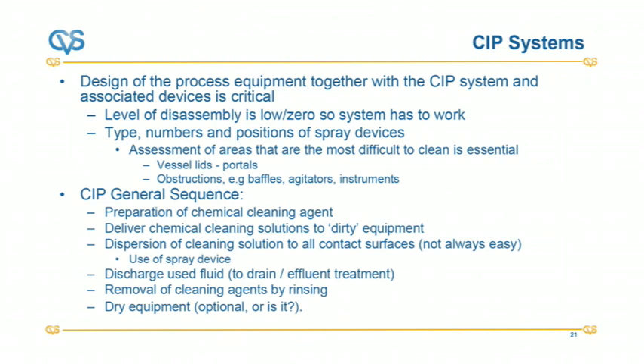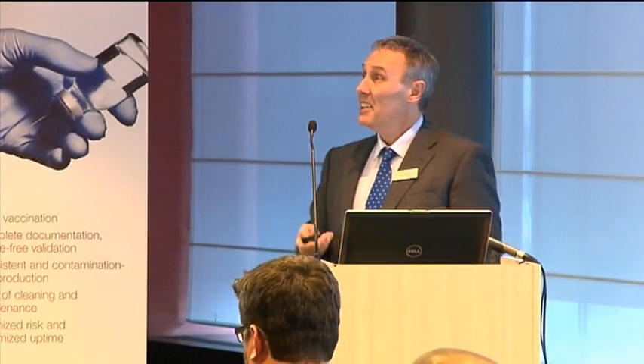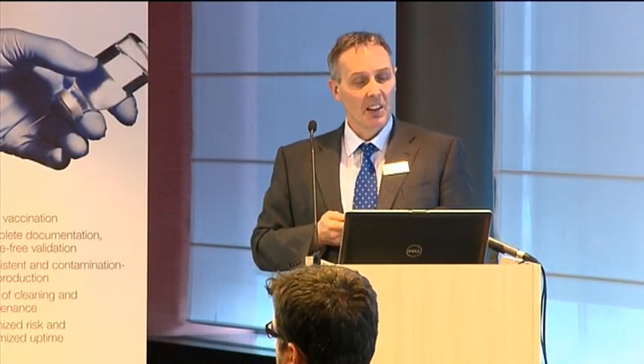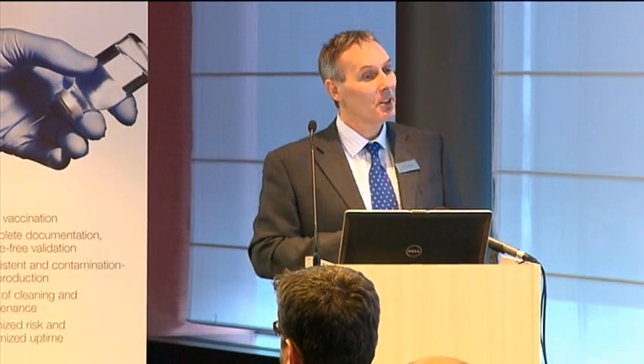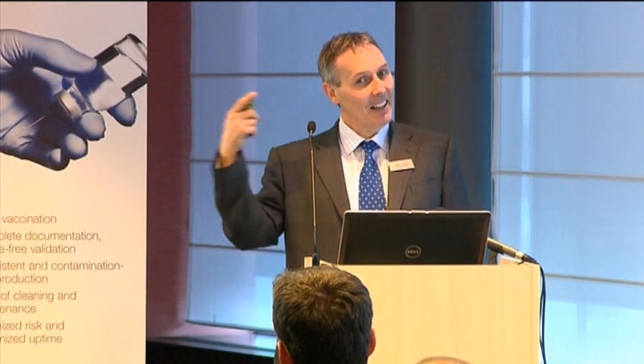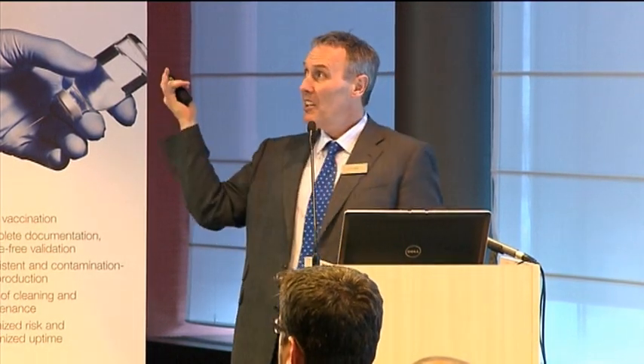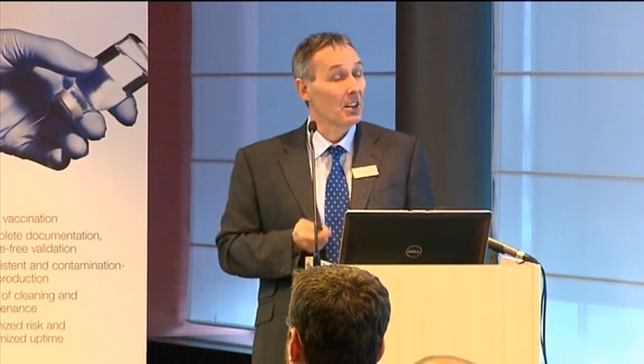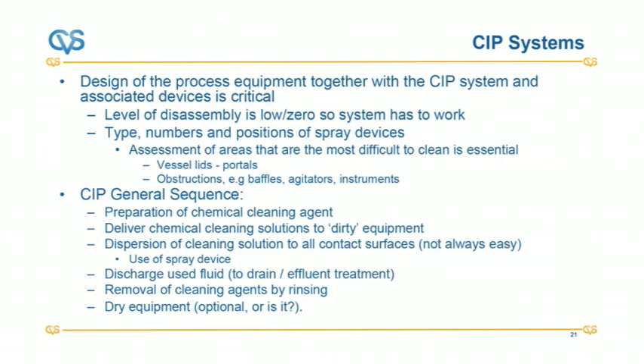We don't want that. Now, the other thing is the type of spray nozzles that we use in that system and their positioning becomes very critical as well. Now, to do that properly, it needs to be all done at the design phase. And this is why sometimes retrofitting can be quite difficult to do. If you can do it with the design phase, it all helps. But basically, you want to assess the areas that are most difficult to clean when you're looking at how you're going to clean the tank. And some of the biggest areas are the vessel lids, so the portals or nozzles, as they're called, obstructions, baffles, agitators, instruments that actually intrude into the area.